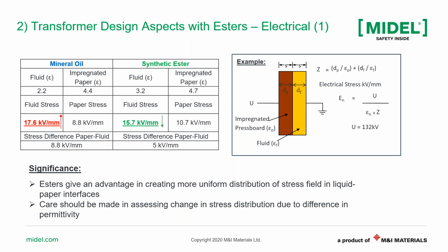And back to the table now, we can see for mineral oil, if we do the calculation, as you can see in the example, the fluid stress is 17.6 kV per millimeter because of the lower permittivity, 2.2, in the oil gap. Comparing that with the synthetic ester, you can see there's a reduced stress in the oil gap to 15.7 in the table, the green one. And so this will give an advantage when using esters in a transformer because it will reduce the stress in the oil gap compared to the solid insulation.